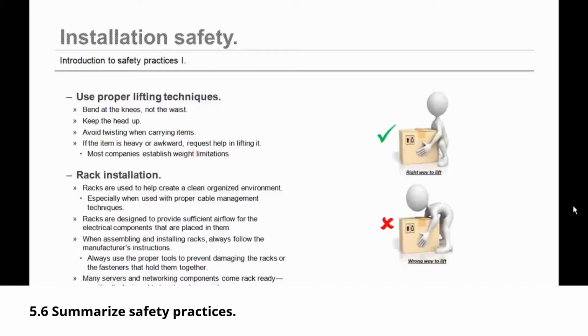More than likely, you are going to need to install equipment racks at some point in time or another. Racks are used to help create a clean, organized environment, especially when they're used with proper cable management techniques. Racks are designed to provide sufficient airflow for the electrical components that are placed in them. When assembling and installing racks, always follow the manufacturer's instructions. Always use the proper tools to prevent damaging the racks or the fasteners that hold them together. Many servers and networking components come rack ready. That means they're specifically designed to be placed into an equipment rack.